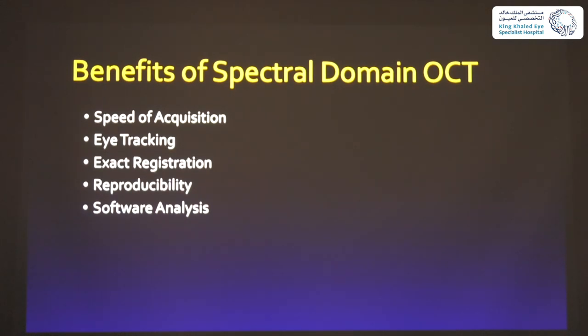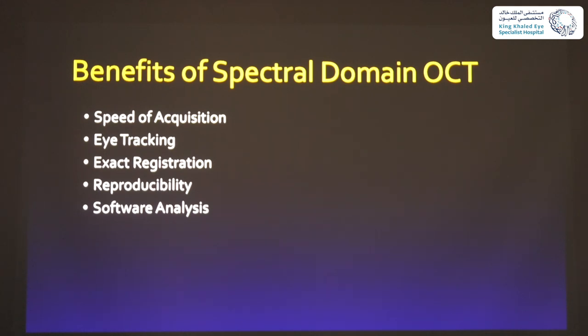The benefits of spectral domain OCT include speed — people don't have to hold still for a long time — and eye tracking, since everything goes in very fast so the machine keeps the point of fixation in the same place. Exact registration is very helpful for follow-up examinations: the machine registers where it took the image based on vessel landmarks, and next time the patient comes in, it will put itself in exactly the same place so you can compare. Reproducibility and software analysis are also key advantages — the software analyzes thicknesses for you.